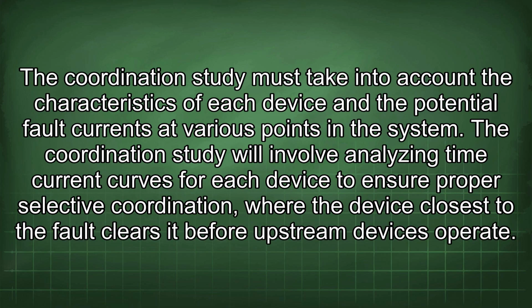The coordination study must take into account the characteristics of each device and the potential fault currents at various points in the system. The coordination study will involve analyzing time current curves for each device to ensure proper selective coordination, where the device closest to the fault clears it before upstream devices operate.